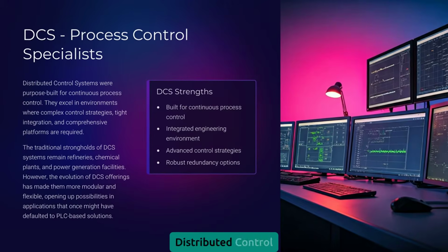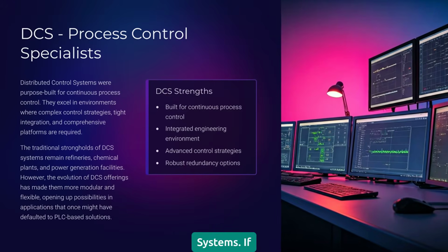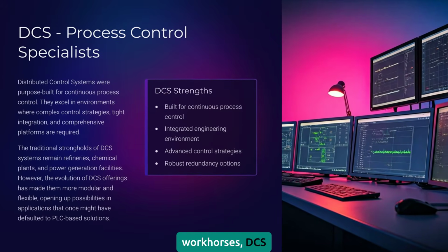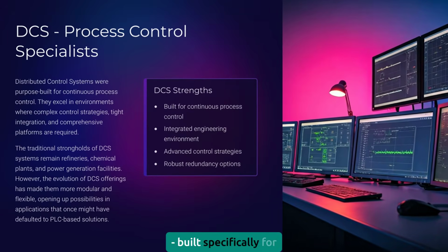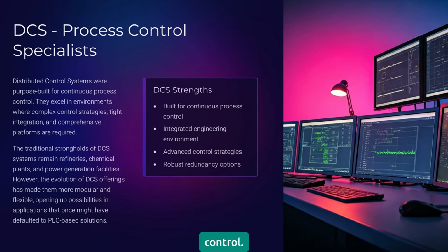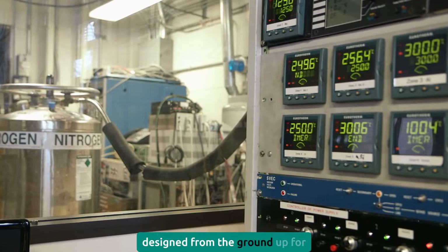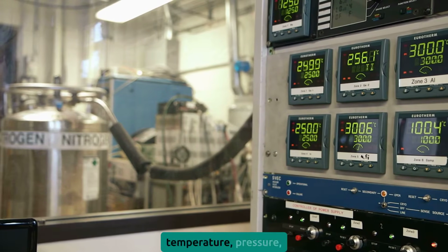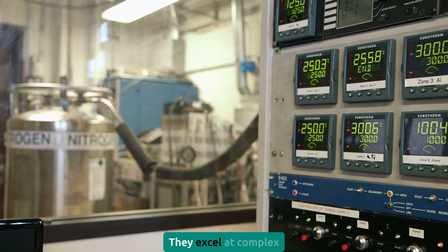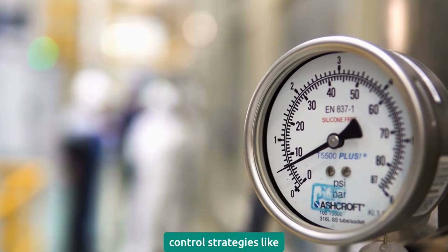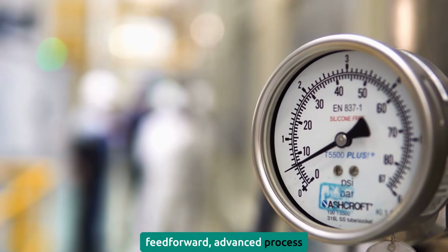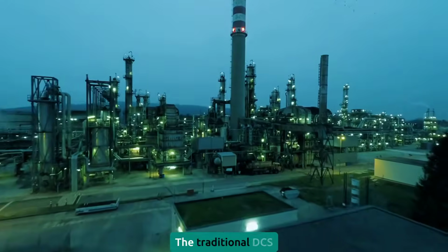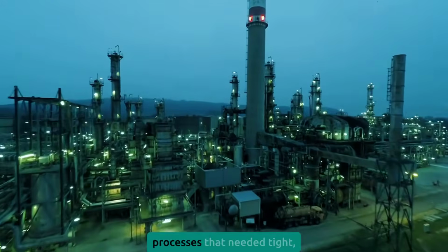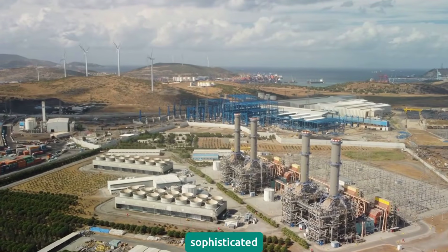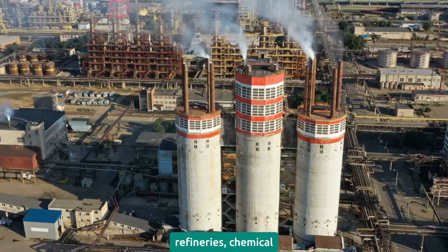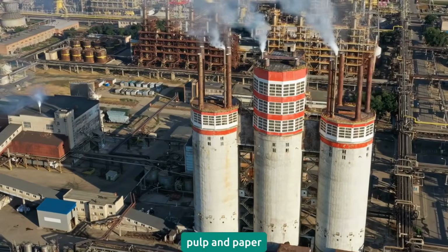Now DCS, distributed control systems. If PLCs were traditionally your workhorses, DCS systems were your thoroughbreds, built specifically for continuous process control. DCS systems were designed from the ground up for analog control: temperature, pressure, flow, level. They excel at complex control strategies like cascade control, feed-forward, and advanced process control algorithms. The traditional DCS sweet spot was continuous processes needing tight, sophisticated control, like oil refineries, chemical plants, power generation, and pulp and paper mills.